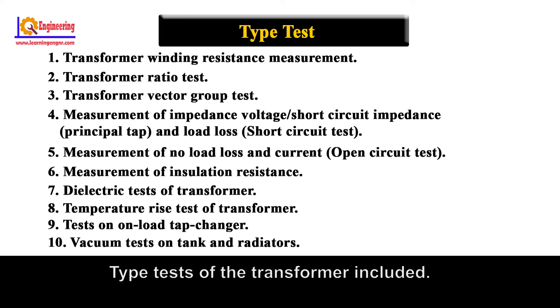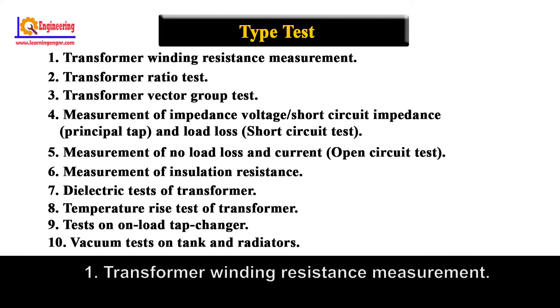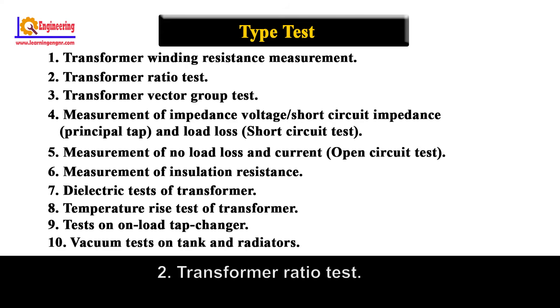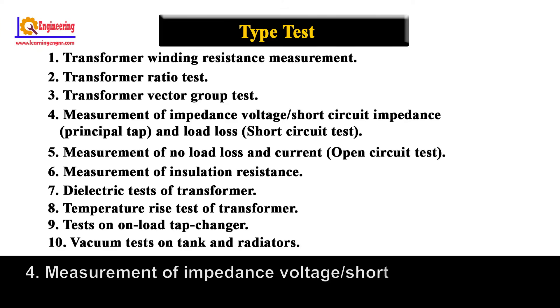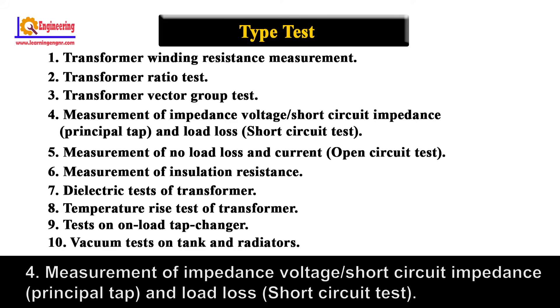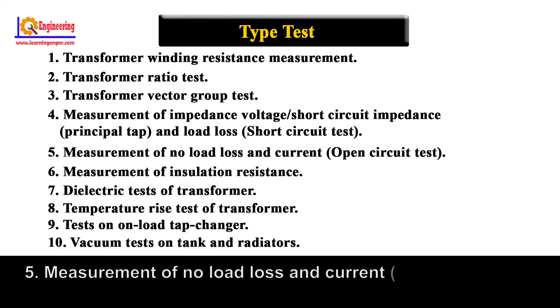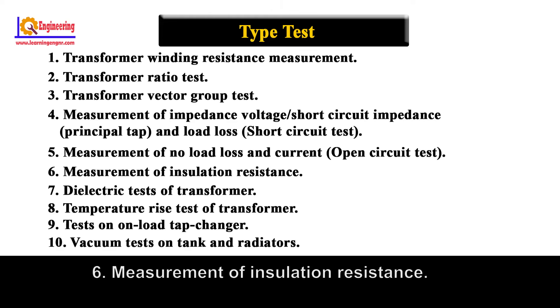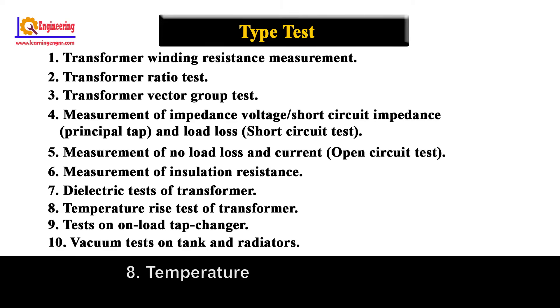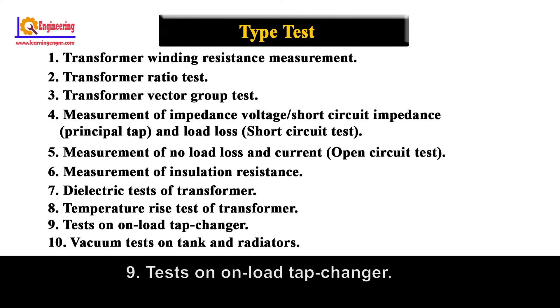Type test of the transformer includes: Number 1, Transformer Winding Resistance Measurement; Number 2, Transformer Ratio Test; Number 3, Transformer Vector Group Test; Number 4, Measurement of Impedance Voltage or Short Circuit Impedance at Principal Tap and Load Loss (Short Circuit Test); Number 5, Measurement of No Load Loss and Current (Open Circuit Test); Number 6, Measurement of Insulation Resistance; Number 7, Dielectric Test of Transformer; Number 8, Temperature Rise Test of Transformer; Number 9, Test on On-Load Tap Changer; Number 10, Vacuum Test on Tank and Radiators.